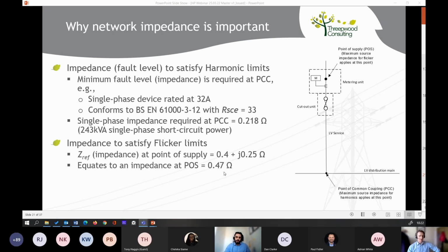So just to clarify, the first point here was harmonics, and you took an example of a 32 amp device tested to G5/5. The Rsce is assumed as 33, that's the default. So you've used that value and the 32 amps to determine an impedance of 0.218 at this mains cable position. Yes, that's correct. And this is the Z-ref, the default unconditional value in G5/5 - that applies at the meter position.